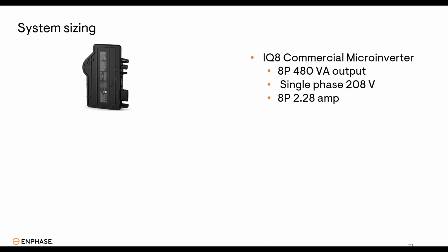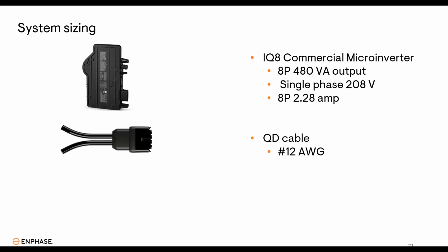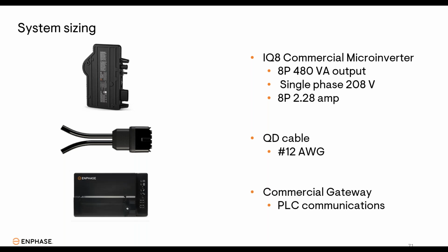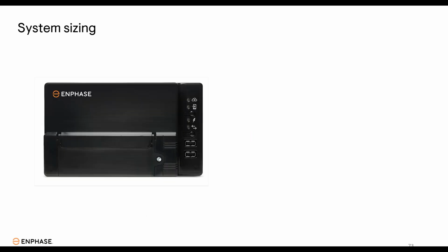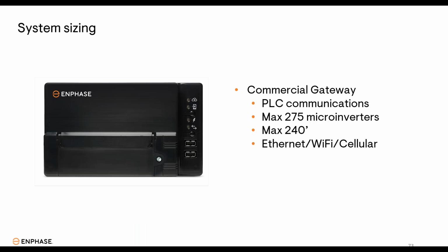The three components that will influence your system design the most are the microinverter, the QD cable, and the gateway. So the gateway uses power line communications to communicate with each microinverter. It is capable of communicating with up to 275 microinverters with a maximum conductor length of 240 feet.